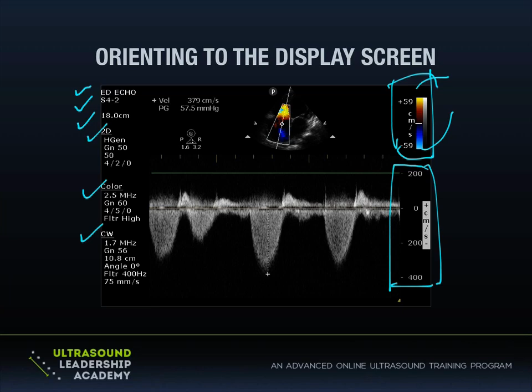Continuous wave Doppler is a really interesting mode. It actually requires at least two crystals inside the transducer, and one is constantly transmitting ultrasound into the tissue. It's not even a pulse, it's a constant beam, a constant stream of ultrasound transmission, while the other crystal is constantly listening. That flies in the face of all the other imaging that we do, where you pulse, listen for a long time, pulse, listen for a long time. Continuous wave is just that, it's continuous.